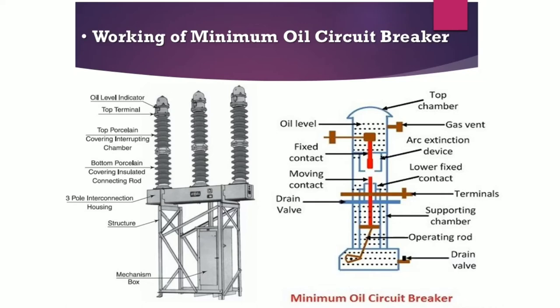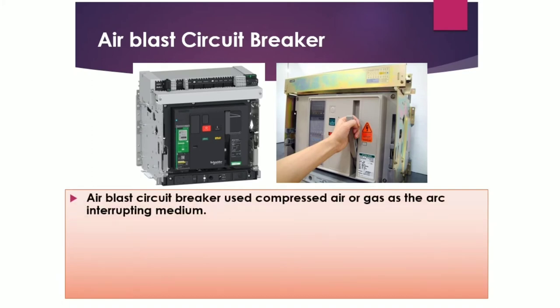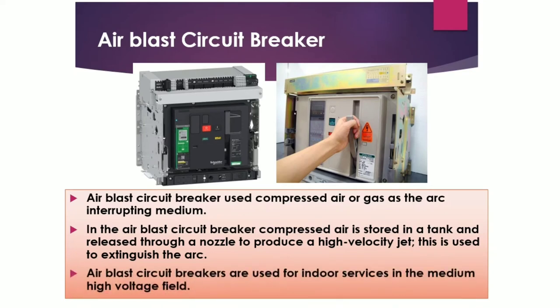In the air blast circuit breaker, compressed air or gas is used as the arc-interrupting medium. The compressed air is stored in a tank and directed through a nozzle to produce a high-velocity jet, which extinguishes the arc. The air blast circuit breaker is used for indoor service in the medium to high voltage field with medium rupturing capacity.